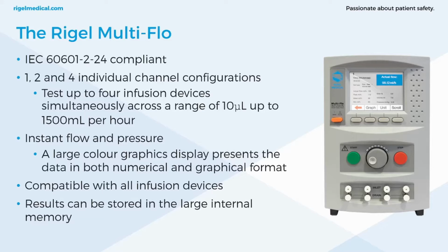Okay, so the Rigel Multi-Flo is IEC 60601-2-24 compliant. Got 1, 2 and 4 individual channel configurations. You can test up to 4 infusion devices simultaneously across a range of 10 microlitres up to 1500 millilitres per hour. It's also upgradable, so if you've purchased the 1 channel configuration Multi-Flo, or you're intending to purchase just the single channel and you're not sure if you want to upgrade at a later point, you can do that. It's a relatively straightforward procedure. You can always upgrade to 2 or 4 channel configuration at a later point.